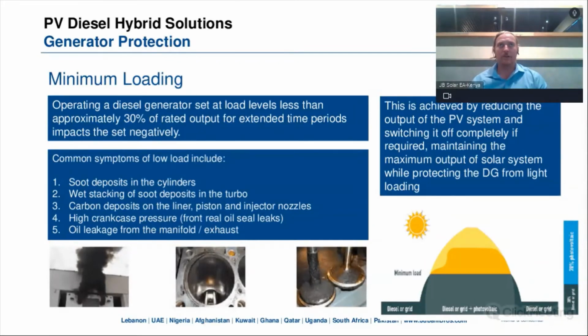So basically, it will shorten the life of your diesel generator. If you operate your diesel generator below the minimum rated load, it will cause damage and shorten the life and void your warranty of the diesel generator. So the fuel save controller maintains the minimum rated capacity of your diesel generators. So that's one function that it has. And the way it does that, you can see on the load profile on the bottom right, it has the minimum load on the diesel generator, and everything above that is from the solar energy.